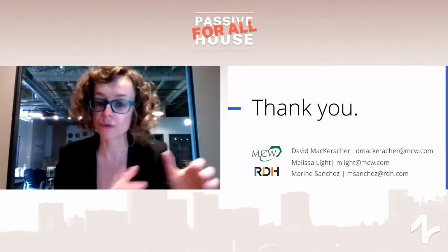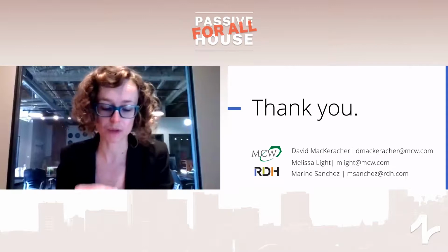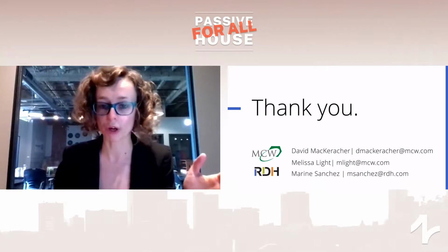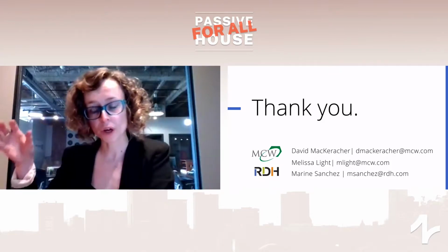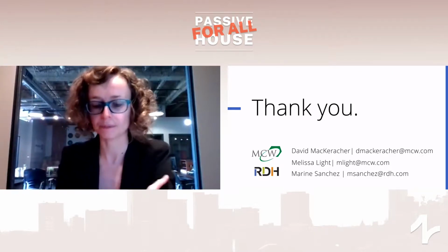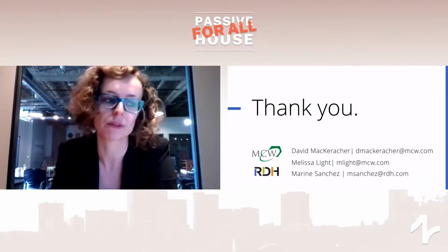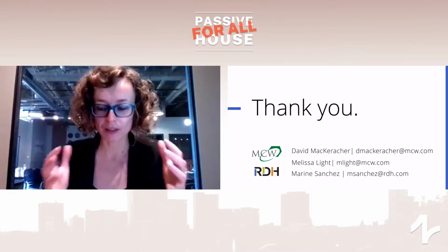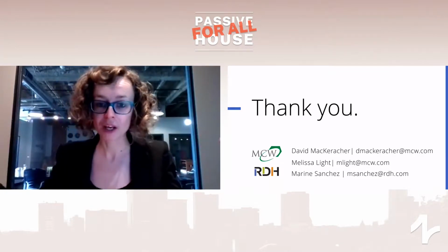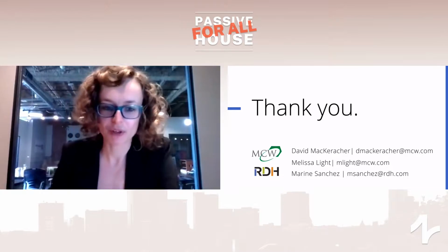for the refrigeration system. So for the UVic building residences, the kitchen is so big that we were able to have the refrigeration system, so walk-in fridges and freezers, with a separate compressor that was linked to a common loop where the waste heat would help preheat the domestic hot water. For UTSC, the sizes of the fridges, the number, didn't make financial sense to then try to get them all onto that one system and then recover some of that heat. So again, a few subtleties around the size and when each measure makes sense on these different sizes. And I think we've started to figure it out on the very, very big, but the challenge now is going to be to keep reducing and see how many of these measures we can keep. So very interesting work.